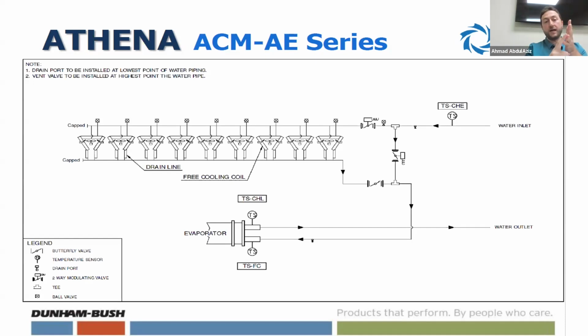You can utilize it at very low ambient temperature, 100% free cooling. That means zero mechanical load from your compressors. So you are switching off your compressors. You are not paying for your power, but you are utilizing 100% free cooling from that integrated coil with your EC fans. We use a logic where the EC fan will be like a shared EC fan based on your ambient temperature. We need a delta T of around 5 between your supply temperature and the ambient, so the free cooling can work.